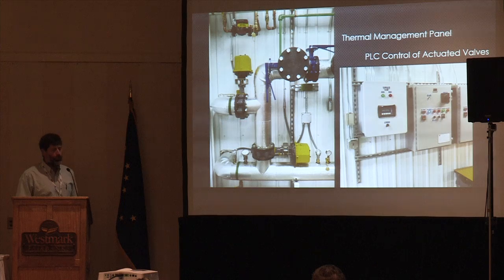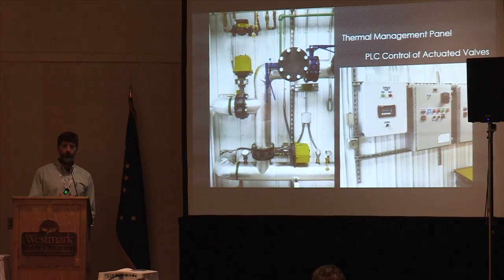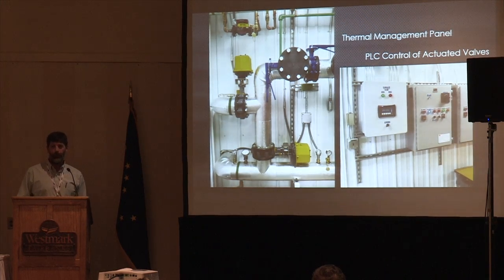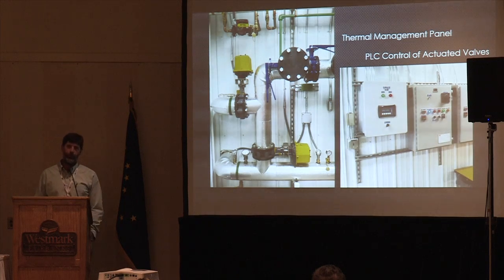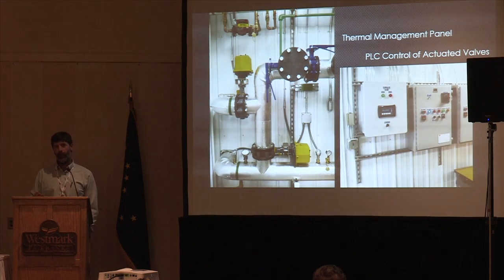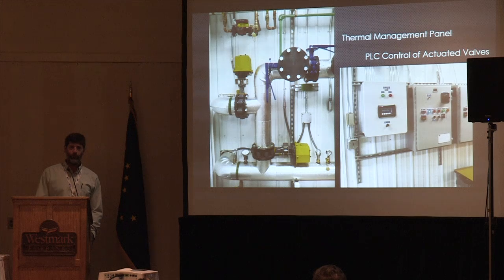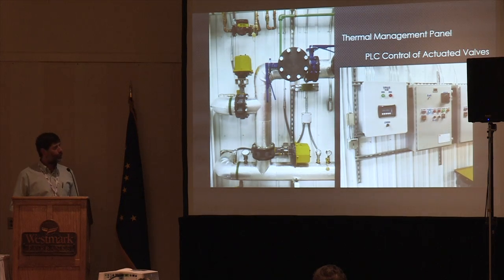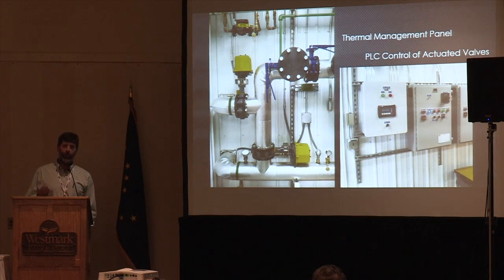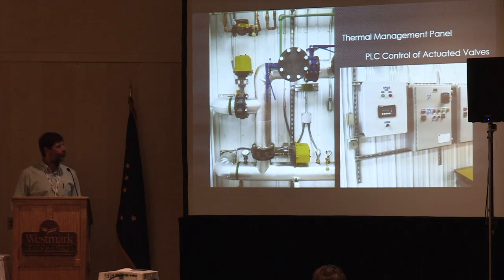We used to have what you call an AMOT valve in a three-way position, and it's pretty much like a thermostat on your engine. When the engine gets warm, the AMOT valve would open, it would bypass or send coolant out to a radiator, then it would come back. They work, but they're not as precise as you might want if you were looking for a minimum water temperature.